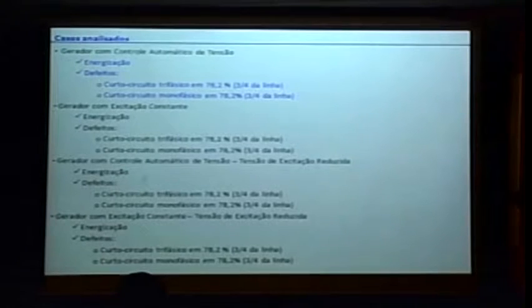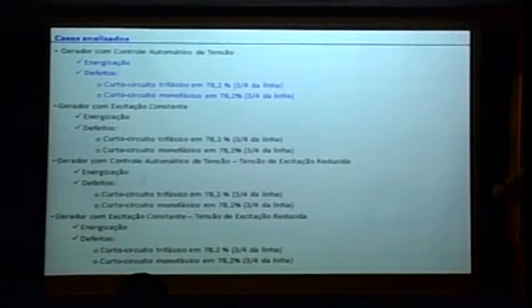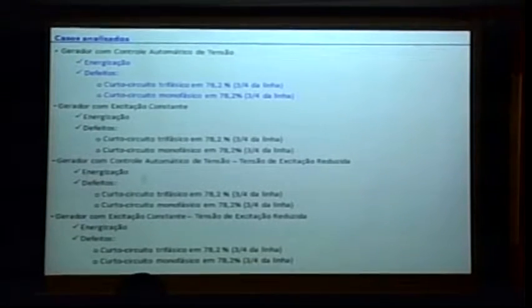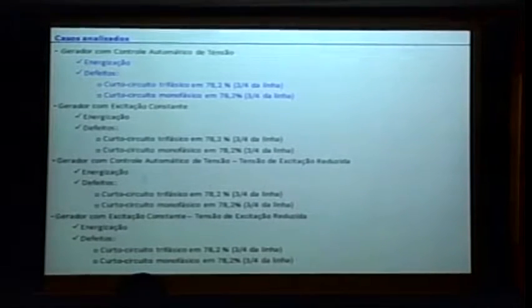We carried out energization tests, and after energization during the test, the fault, three-phase and single-phase faults, short circuits. I'm going to show that at 3/4 of the line, which are the worst cases as it's known. Then we did the test with the constant excitation, so during the whole event the AVR does not update the field current in the machine. I'm not going to show you this here, but this is in the report.